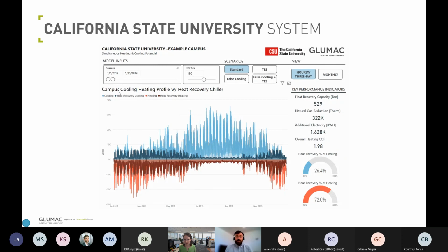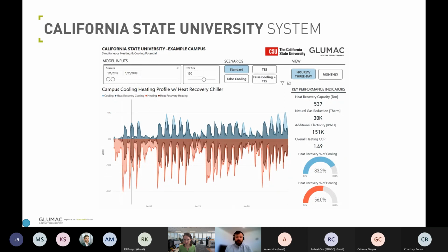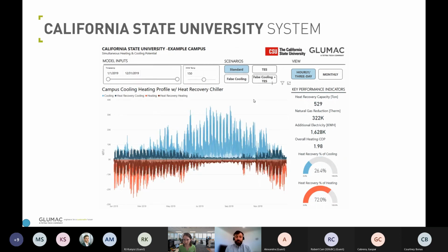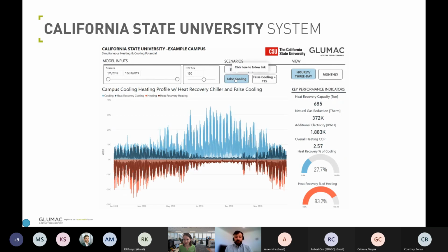We can also drill into specific periods. So this shows in the winter how there are periods where we have excess heating where we would not be able to meet that with a heat recovery chiller. But there's also opportunities in the afternoons where we have excess cooling. So this shows, we can add thermal energy storage and increase that potential. Looking at different scenarios around thermal energy storage or false cooling. False cooling is a strategy where we reduce the amount of time that economizers work, and we can recapture heat through the chilled water system at the air handler. And that strategy alone will increase that heat recovery potential up to 83.2%. So we're able to, just through some simple optimization of existing infrastructure, increase the ability to recapture heat.